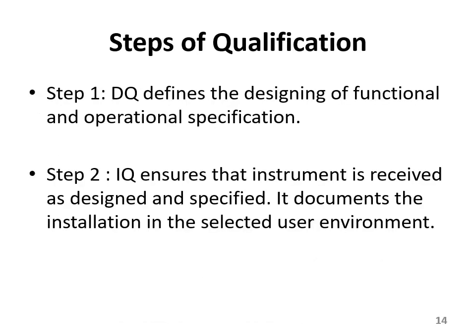Steps or the phases of qualification. Step 1, design qualification, DQ. This defines the functional and operational specification of a balance, instrument, or a process, right?